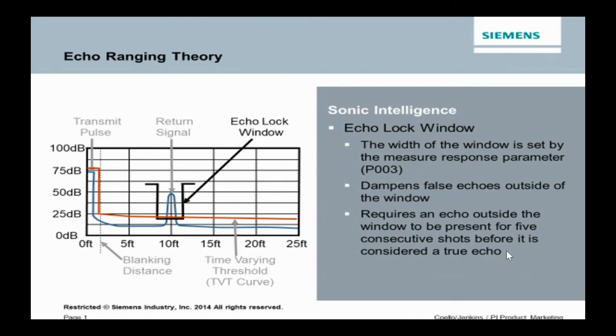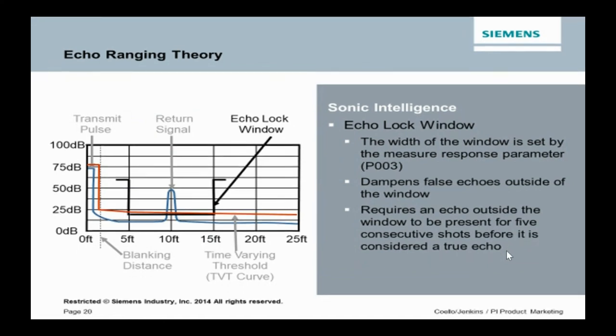it sees an agitator blade, it's going to go, huh, I see a new echo, but it's outside of my echo lock window, so I'm not going to react to it right away. I'm going to wait, and by the time it takes its next measurement, that agitator blade has moved out of the way, and it goes, ah, okay, never mind, I'll stay stuck on this. If you set this thing to fast and you open this filter up, it's going to say, oh, I see something new. It's inside the window. I'm going there right now.